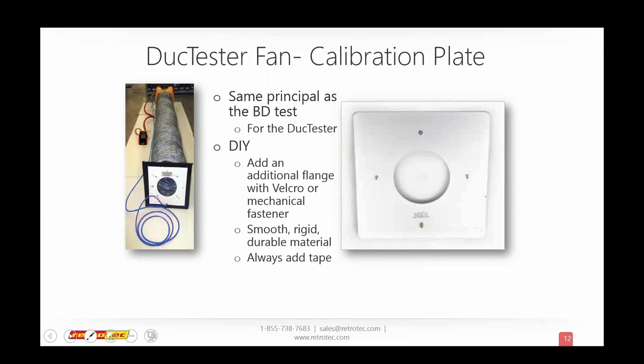So if you could chime in as to what gauge you have, DG700, DM32, DM2, it doesn't matter if you have Wi-Fi or not. But for those of you that do have the DM32, the thing that Jay is referring to and Colin about how to get your leakage area, to make sure we're on the same page, if you go to your settings, it actually allows you to determine what results you want. You can also pick that from channel B, and it starts off with pascals and CFM, and then a flow area, CFM per 100 square feet.